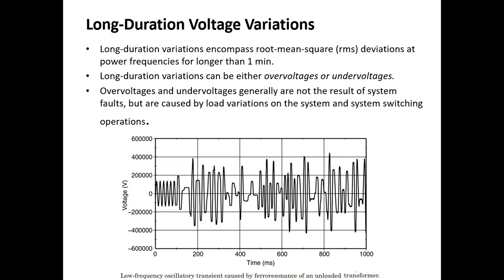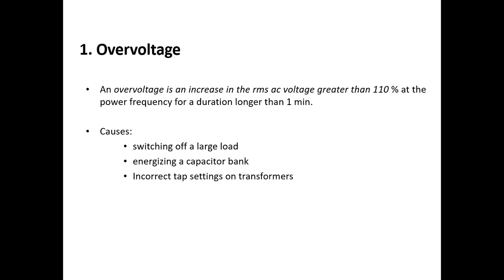Now this is the diagram. In this diagram, low frequency oscillatory transients are caused by the ferroresonance of an unloaded transformer. You can see the pattern, and how the long duration voltage variations change if the ferroresonance condition of an unloaded transformer is there. From this diagram you can see that these are long duration voltage variations.